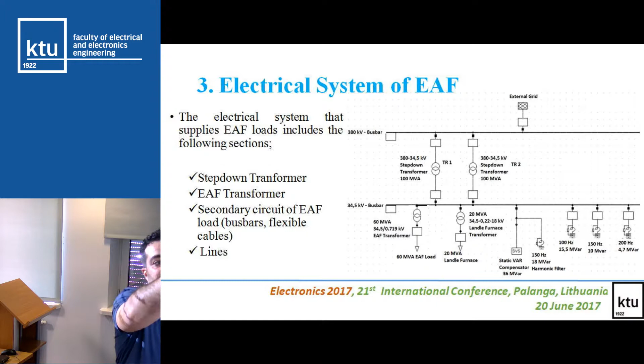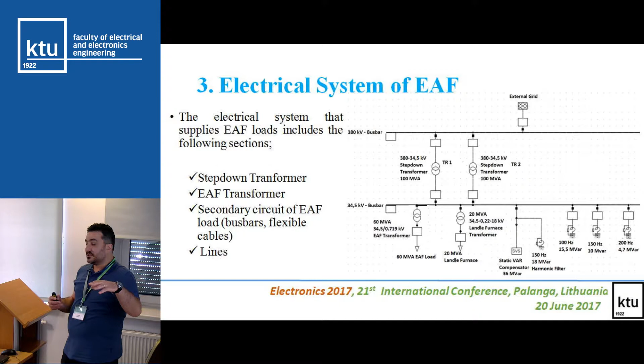Looking at the system, we have a high voltage bus bar and a middle voltage bus bar, with 2 transformers feeding the electric arc furnace load, along with harmonic filter groups and static var compensation groups. In my work, the facility didn't allow me to take the harmonic filters out of the system, so I measured only with these systems on. Here is the single line diagram.